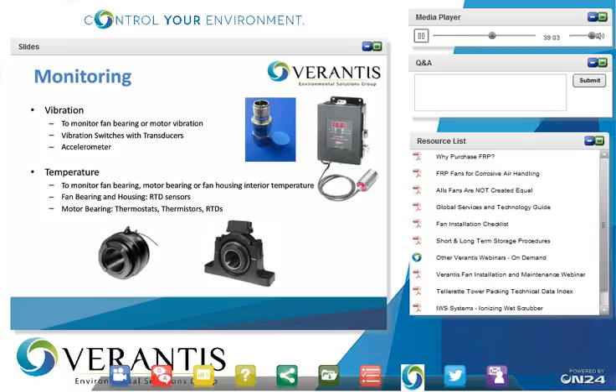It usually will be beneficial to monitor fan bearing vibration or the motor vibration level. The picture on the left is an accelerometer. It's going to be sensing the vibration and sending the signals over to the control panel. And the picture on the right shows a vibration switch with transducers, which is going to do the sensing as well as control.